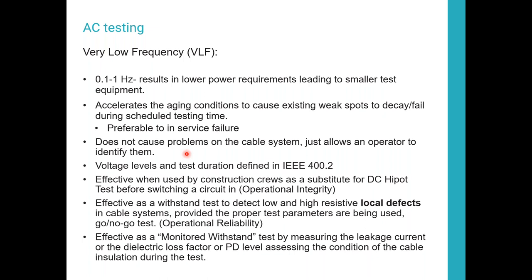It does accelerate the aging conditions to cause existing weak spots to decay or fail during testing time, not in service. And what they're able to do with these, and we'll get into these a little bit further, is a voltage sweep. They're able to apply voltages increasing in steps until they actually see a PD breakdown.